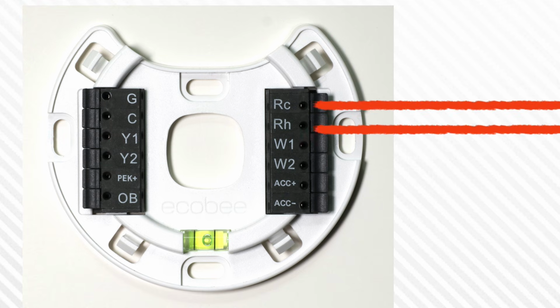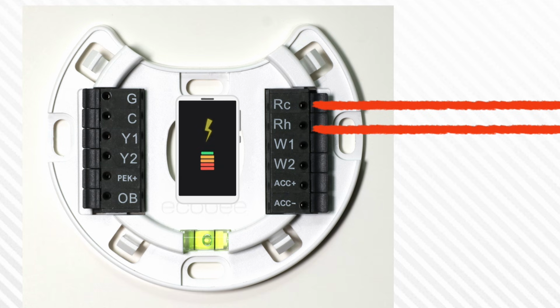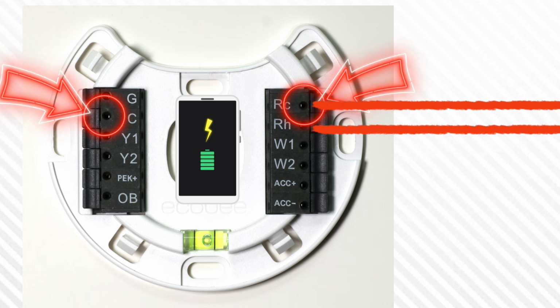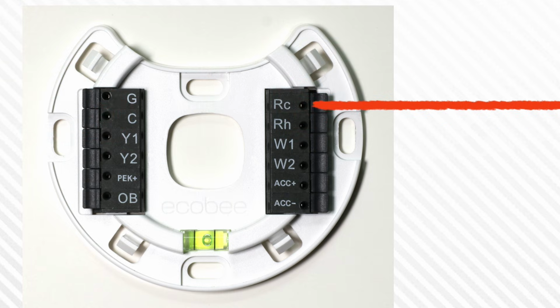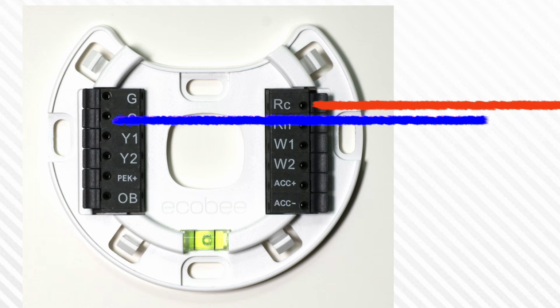When you have two wires hooked up to each of these R terminals, that jumper is deactivated. So the only way the thermostat can charge off of that RC terminal is if the common wire is coming off of the AC system, because taking 24 volts off of one transformer and connecting it to a common on a different transformer just doesn't work. The only time using a common wire from a boiler works is when you're just hooking up heating with no air conditioning. You land that power wire on RC, and then your common can go back to the boiler and it'll work fine.